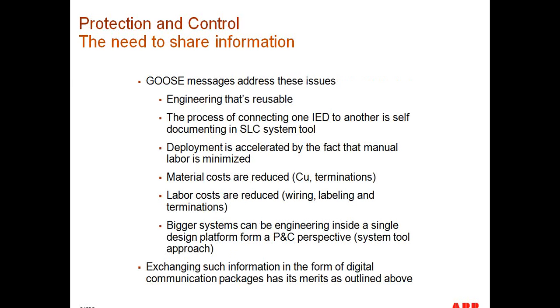Well, one of the things is that the engineering of these associations via GOOSE messages is essentially reusable. It's all in a software platform. It's essentially a digital connection from one device to another. So as long as you're utilizing the same type of devices, the engineering can be pretty much reutilized. There will obviously be changes from one station to the other and from one application to the other, but the engineering is essentially all in software, so it's much easier to manipulate.